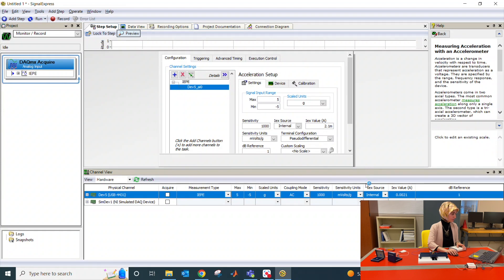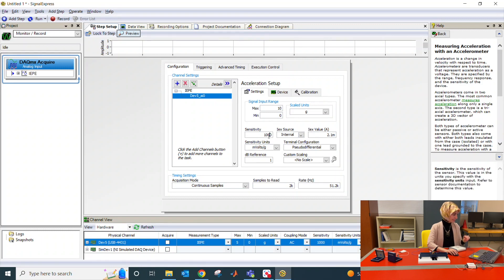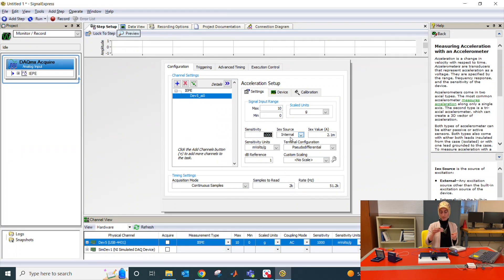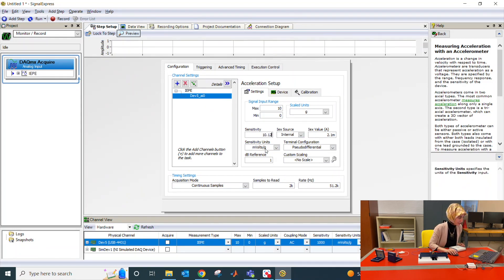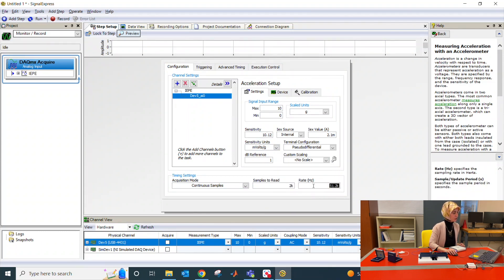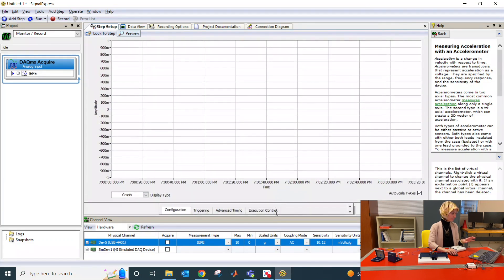Now we have to adjust the settings. Your minimum value will be zero and the maximum will be 10. For sensitivity, let me double-check — in the X direction, from the data spec sheet, it's 10.12 millivolts per G, so the unit is correct. Samples to read is 2K, and you might want to change the rate to also 2K. Once you're done with settings, you can scroll the menu down.